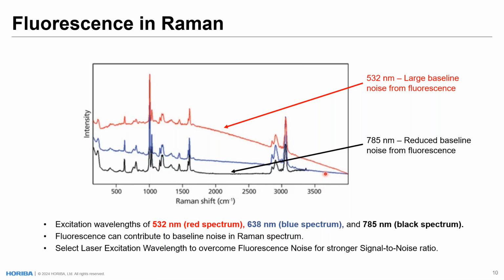So here is a spectrum collected with 3 different laser wavelengths. The red is a 532 nanometer laser, and this black here is a 785 nanometer laser trace. And this is the wavelength that we use in our process analyzers now. As you can see, there is a large arcing baseline noise from the fluorescence with the 532 nanometer laser. But with the 785, when we walk it to much longer wavelengths, that baseline pretty much goes away completely, which allows for a much more resolved and tractable spectrum.